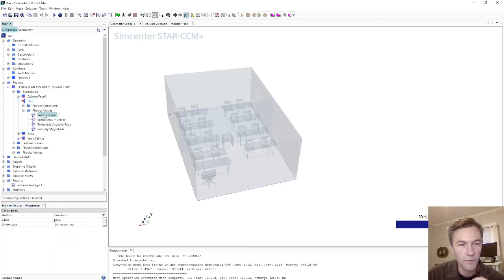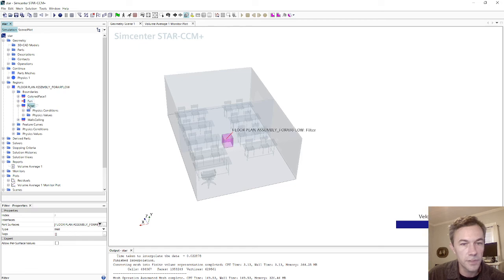And we got a couple of things to define. Let's say that the passive scalar coming on that fan inlet is going to be 0 because the filter's filtered out 100% of that scalar. And let's give it a value of, say, 4 meters a second at the face of the fan. And then the filters themselves, you remember the outsides of our box are going to be the outlet of the model. So we have flow being recirculated from the fan back to the filters by definition.